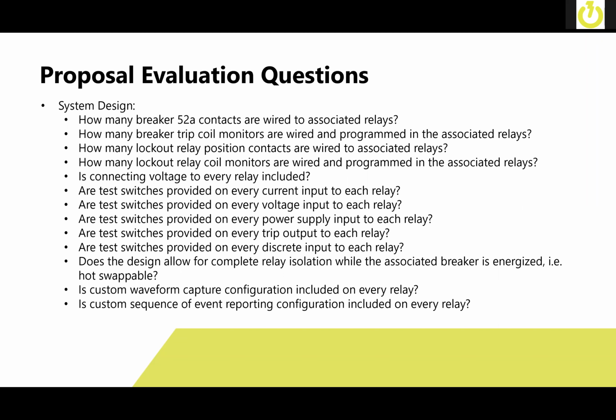From a system design standpoint, ask people how many are hooking up breaker 52A contacts to associated relays. This allows you to aid in event analyses and determine if everything tripped in the sequence that it was supposed to. Breaker trip coil monitors being wired up and programmed in the associated relays. Lockout relay position contacts, lockout relay coil monitors. And what this allows you to do is some preventive analysis where maybe you don't have to get in there with meters on the system.